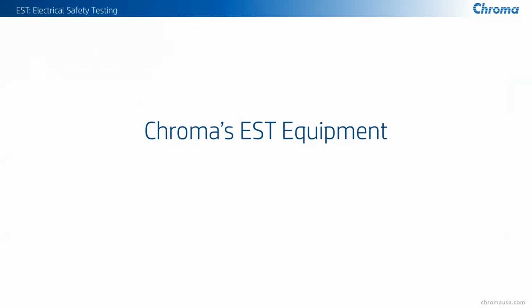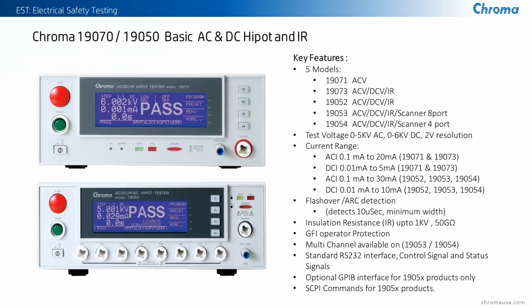So Chroma has a vast number of different types of test equipment to cover all the different needs. And so what we have to offer is based on standard basic AC/DC hipot testers, starting with our 19070 and our 19050 family of products. These will give you a basic AC voltage hipot test, or AC plus DC hipot test, and insulation resistance test. And with these, you can do up to 5,000 volts AC, 6,000 volts DC. Very good resolution on the settings, very accurate on the measurements. So with this one, you can do 2-volt resolution, and depending on which model, you can go anywhere from 20 milliamps of AC current, 5 milliamps of DC current, and you can go 30 milliamps of AC current up to 10 milliamps of DC current.